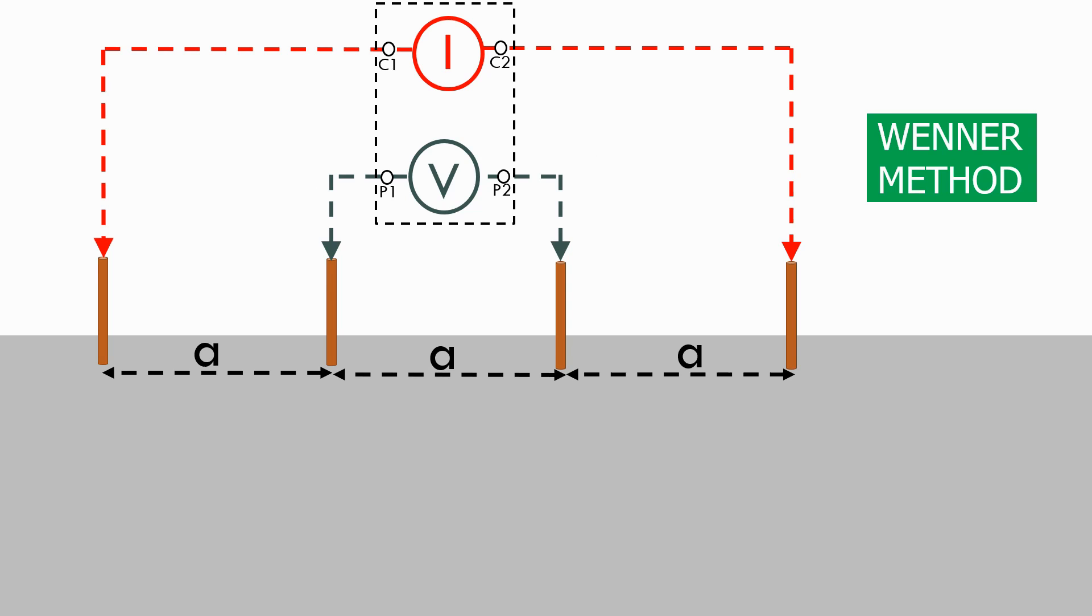The spacing of the rods A defines the depth at which the reading is being taken, as the current between the two outer rods flows through the ground in a parabolic fashion. So by varying the spacing of A we can change the depth at which we're measuring the soil resistivity, which can be very useful information when we're designing our grounding system.